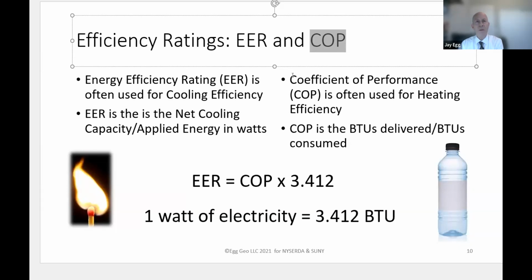And so coefficient of performance is the one I usually focus on, because EER is more of a cooling efficiency rating, and it's more of a US-based rating. The world normally uses COP because it's a very simple equation. Coefficient of performance is the BTUs delivered divided by the BTUs consumed, a very simple ratio. So if you deliver 36,000 BTUs and you consume 12,000 BTUs of energy, then you have a COP of 3, meaning the heat pump is 300% efficient. It's delivering 3 times the energy it's consuming.